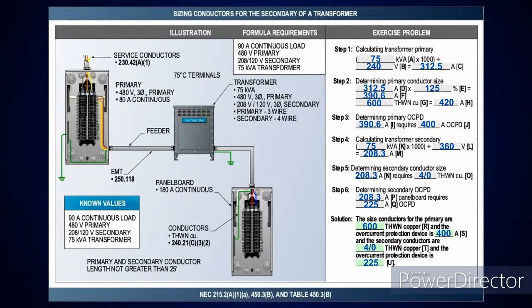Then I look at sizing the overcurrent protection device for that primary. How am I going to determine that? Well, go look at 240.4(B). I'm not exceeding 800 amps. So therefore, I'll have a rule of thumb when we get over to overcurrent protection devices: anything at 125% or less, go up to the next standard size. And then any percentage above that, you're going to drop down. Okay. Now, the only difference in this 125% here is I didn't exceed 800 amps. So therefore, that means I'm going to use the next standard size per table 240.6(A), which is going to be a 400 amp overcurrent device.